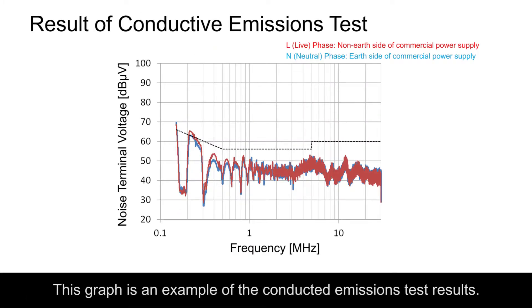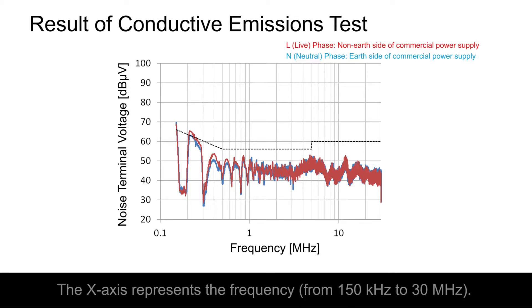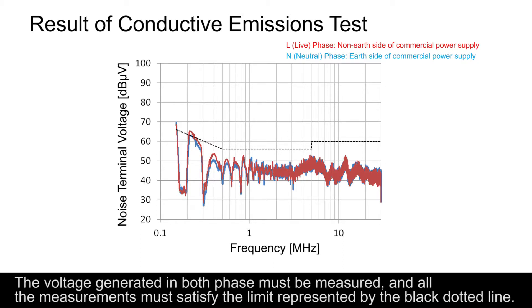This graph is an example of the conductive emissions test results. The X-axis represents the frequency from 150 kHz to 30 MHz. The Y-axis shows the level of the noise terminal voltage. The voltage generated in both phases must be measured, and all measurements must satisfy the limit represented by the black dotted line.